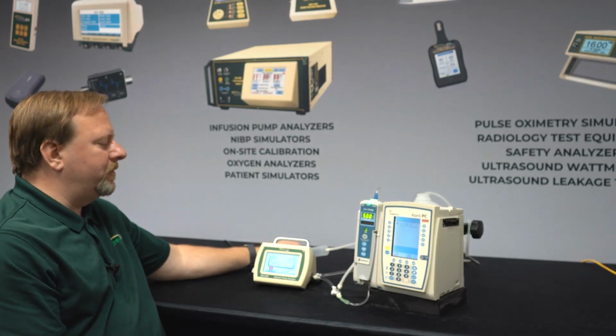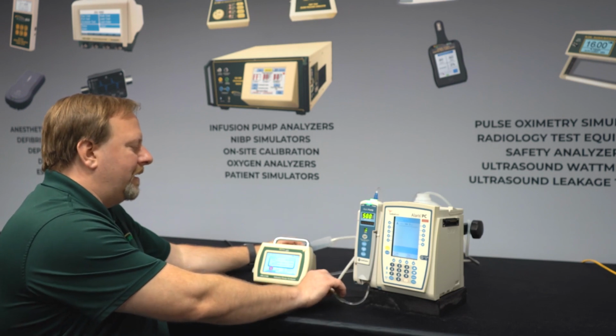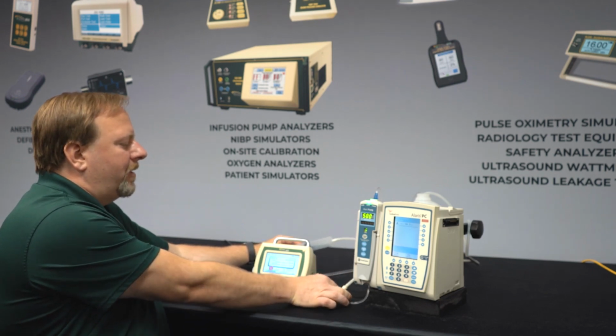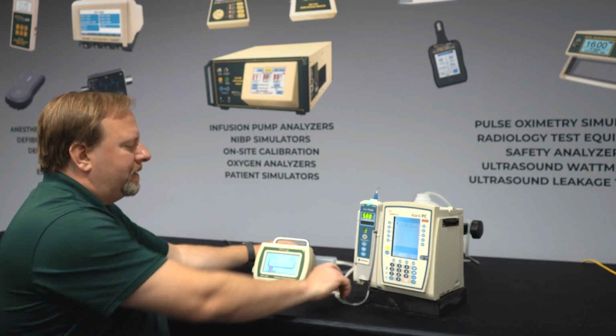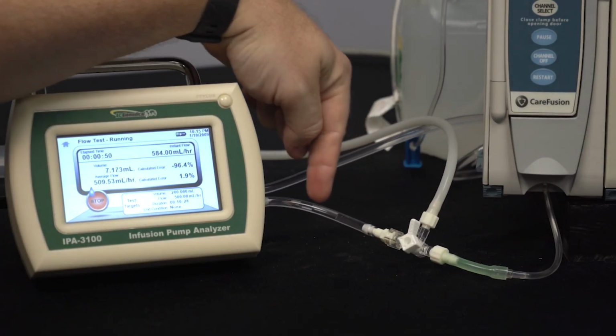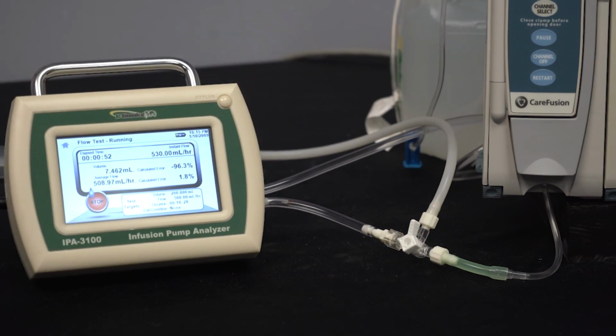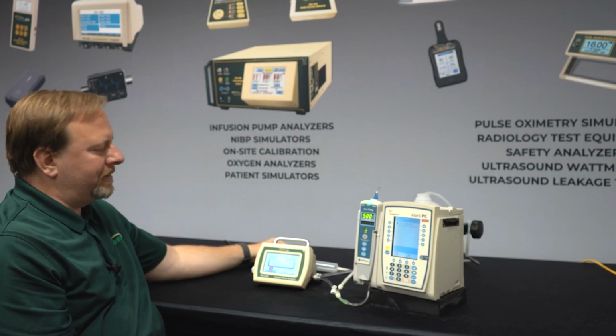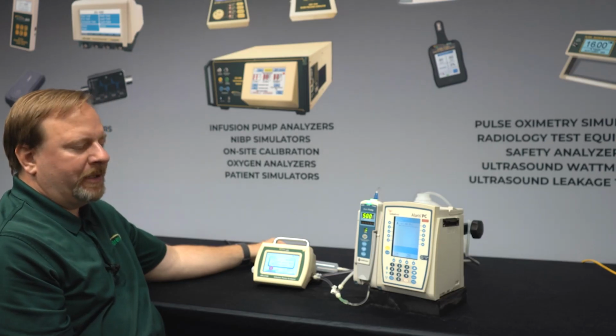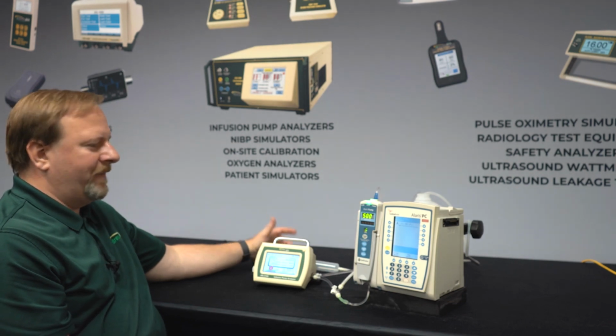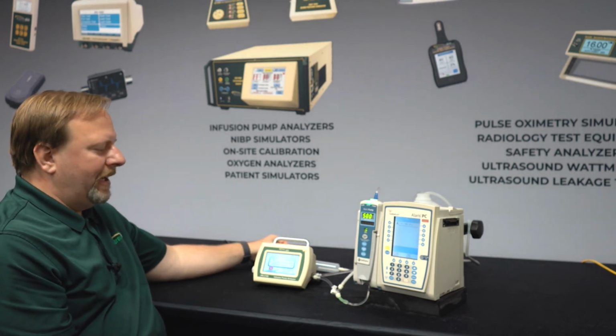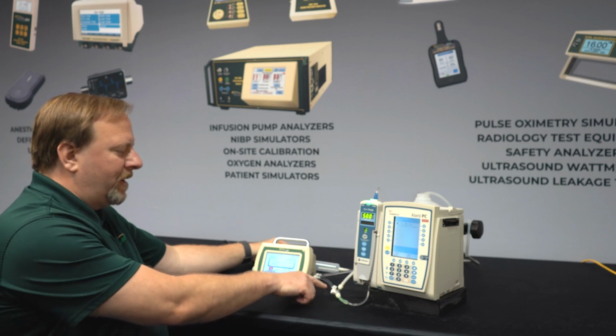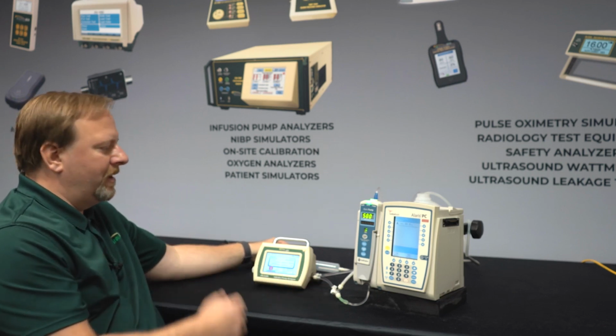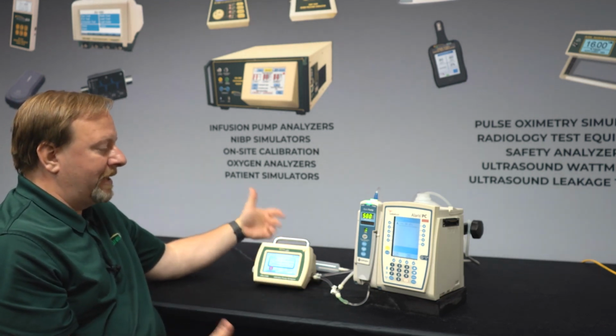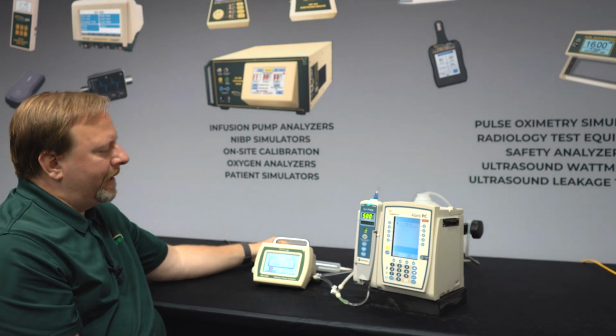So what I'm going to do is switch my valve here, and I'm going to go ahead and introduce some air into the test, and we can see here we've got some large bubbles running in. Now imagine you're running a low flow test and it's been about 20 hours into your test process, and you've got another 20 hours to go, and a bubble dislodges from one of your fittings and it goes into your equipment, canceling your test. So that could be a big deal.